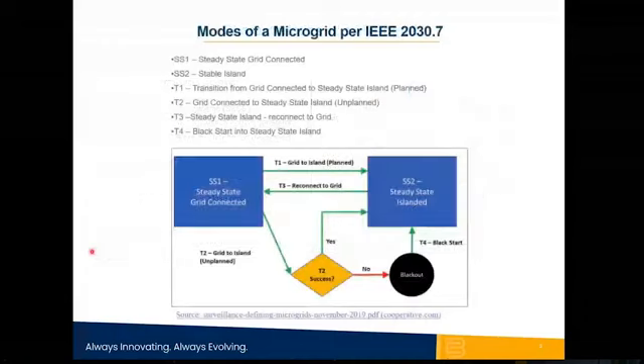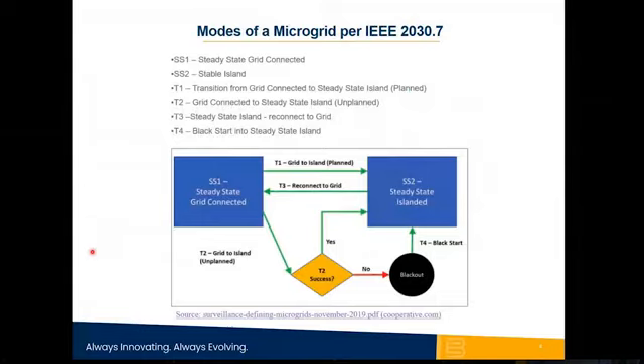So now that we've talked about what a microgrid is and the various unique characteristics of microgrids from a power system standpoint, let us talk about the various modes of operation of a microgrid. There is a standard, and it is the IEEE 2030.7 standard that clearly defines the two states of a microgrid and the various transitions between these states. So the first state is steady state grid connected. That is, you have a microgrid, and at the point of common coupling, there's a physical connection that's made, typically through a breaker. And that is a steady state grid connected state.